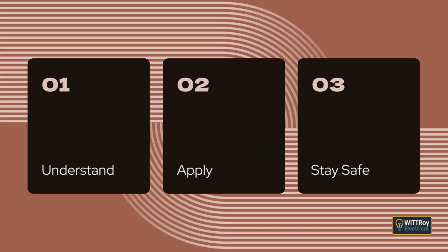Clause 2.9.3.2 Suitability. Switchboards must be strong enough to handle the real-world stresses they face. They need to withstand mechanical stress, electrical stress, and thermal stress that may happen during normal service or during faults. If a switchboard is built to the ASNZS 3439 series, it is considered suitable. That standard sets the performance expected. There are also extra design requirements for segregation of safety services and for protection against arcing faults, which appear in other parts of ASNZS 3000.